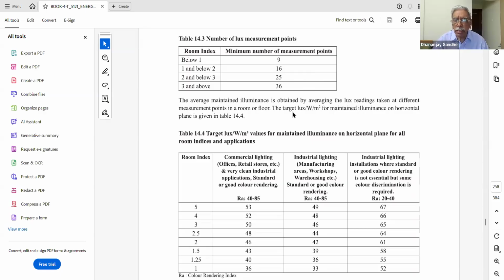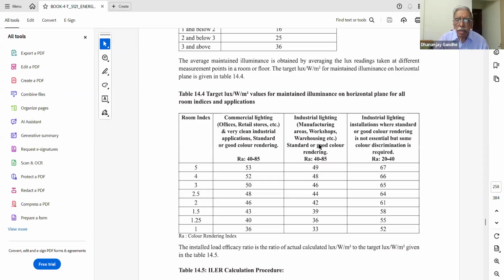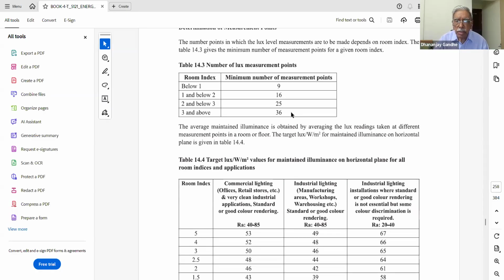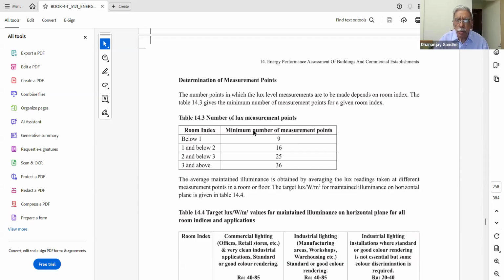That is to ensure that, many times, the illumination in a particular room may not be uniform. So you may take a figure which is actually higher or lower. In order to avoid that incorrectness, they are taking the average value. So this is how you measure the lux based on the room index.